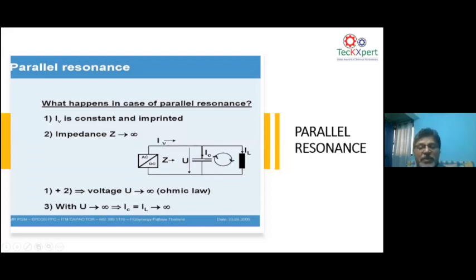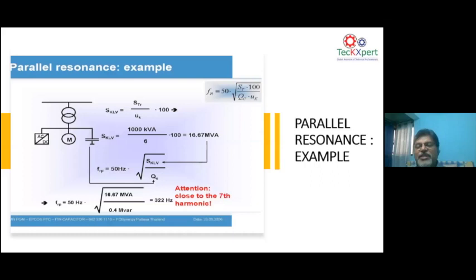And that is how, because when the impedance goes up, for a fixed current source, say the harmonic current generated by a VFD, that is a fixed current source. When the Z of the equivalent circuit becomes infinity, naturally your voltage also goes up, because a fixed current source into infinite impedance means infinite voltage. So in parallel resonance you have two problems. The voltage goes up substantially in the grid, and the current drawn also goes up substantially. That is how equipment failures and fire accidents can happen at parallel resonance time.